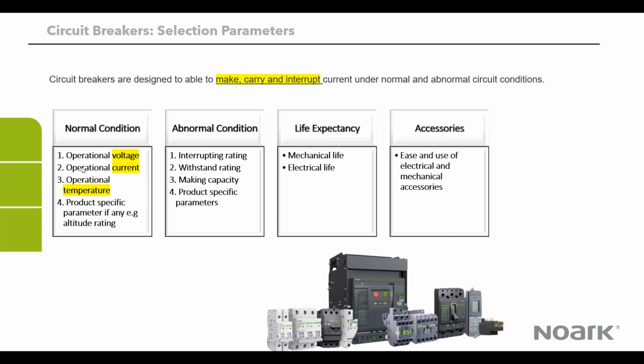The first thing is, under normal conditions, you need to know what the operational voltage is. At what voltage are we going to be using this circuit breaker? The other thing you need to know is the operational current for the circuit breaker. Also, you want to find out the operating temperature. And then, of course, any other product-specific parameter, something like altitude rating, because for every product you have a specific altitude rating. There's also the humidity rating, what kind of environmental condition you can expose the breaker to. So these are all parameters that you must bear in mind when you're trying to select a circuit breaker.